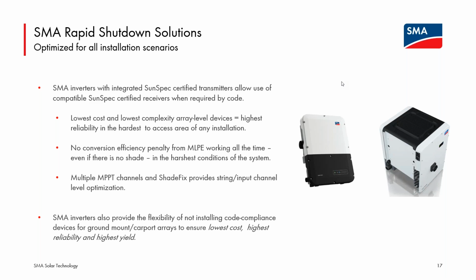The other half of the puzzle for utilizing SunSpec for code compliance is to have a receiver element at the array that is listening for the signal that the transmitter in the inverter generates. And these SunSpec receivers are very low complexity. They don't have to boost or buck DC voltage. They certainly don't have to convert DC current to AC current. They are simply listening for a signal generated by the inverter-based transmitter. If it's present, they allow their modules to operate. If it's not, they isolate their modules from the system, the string they are part of.